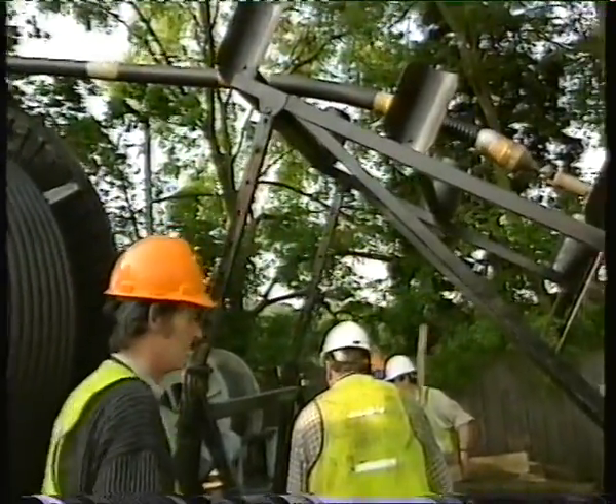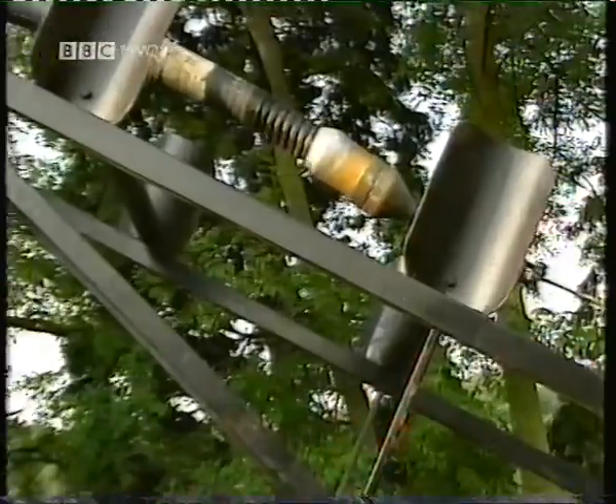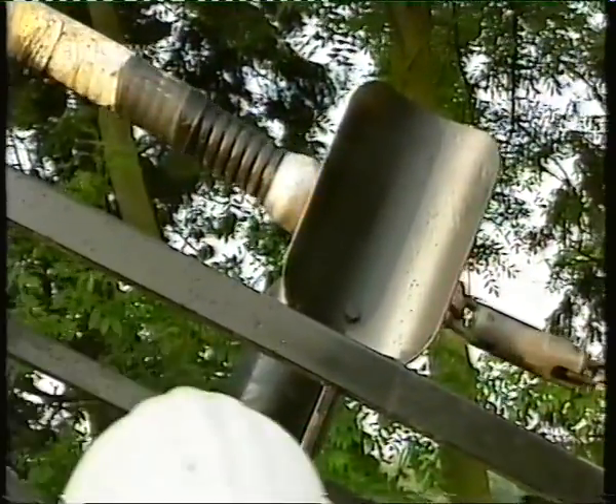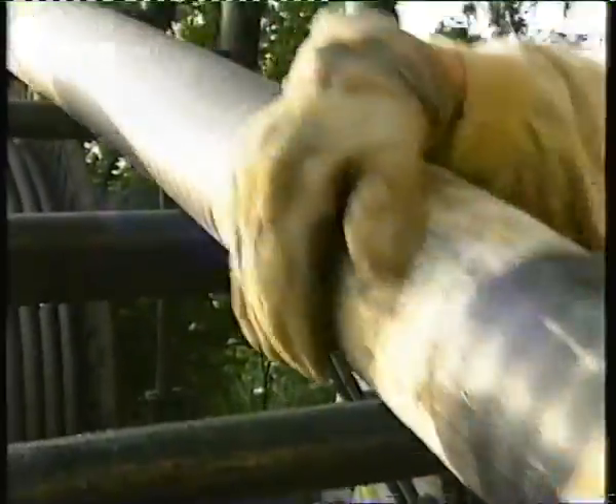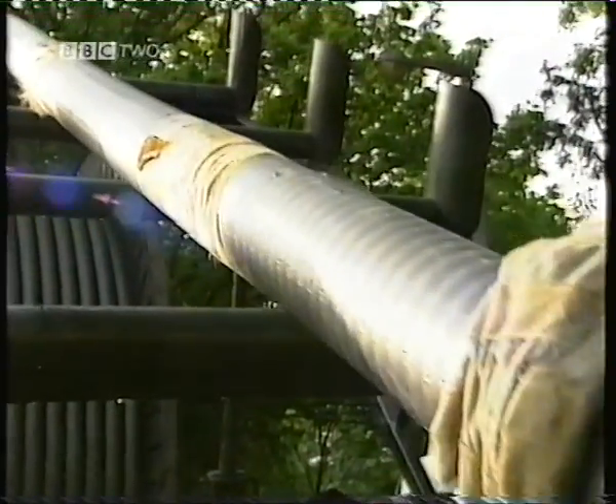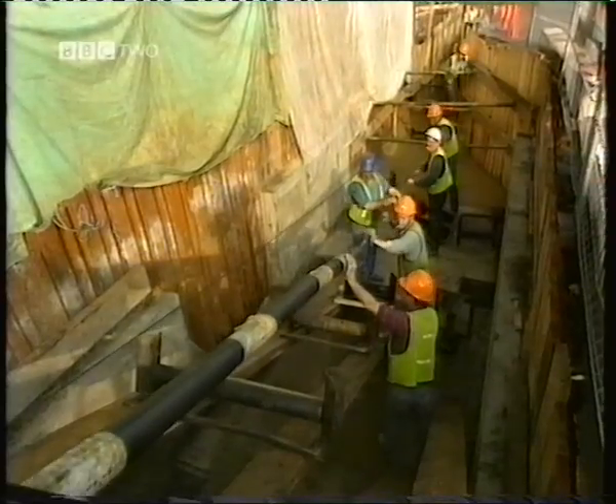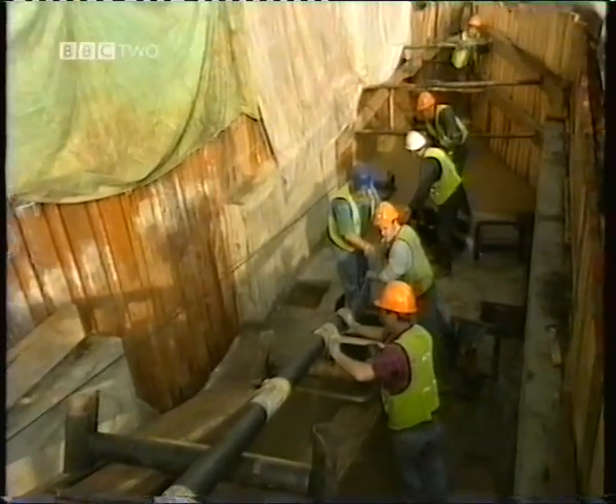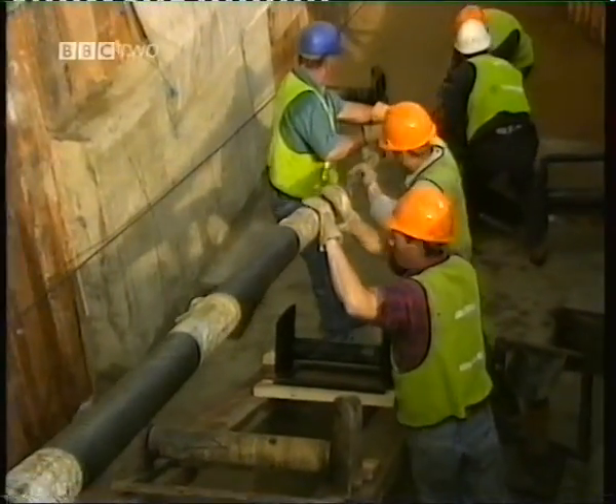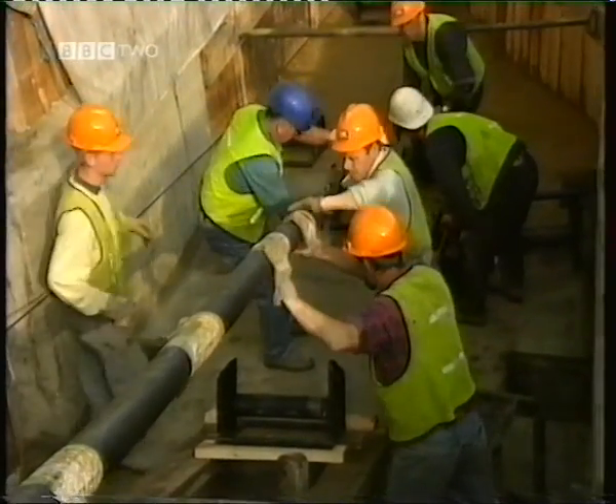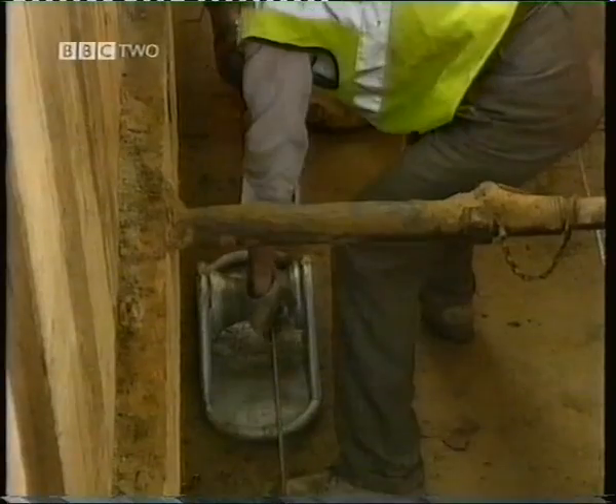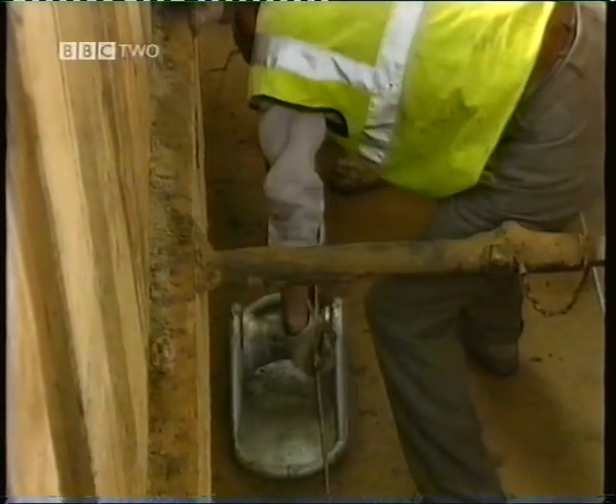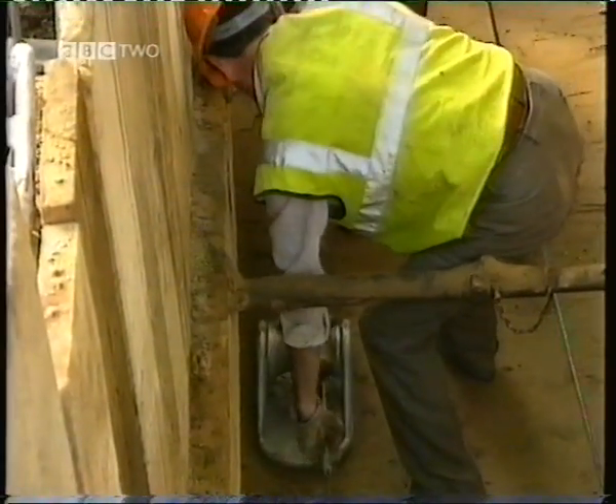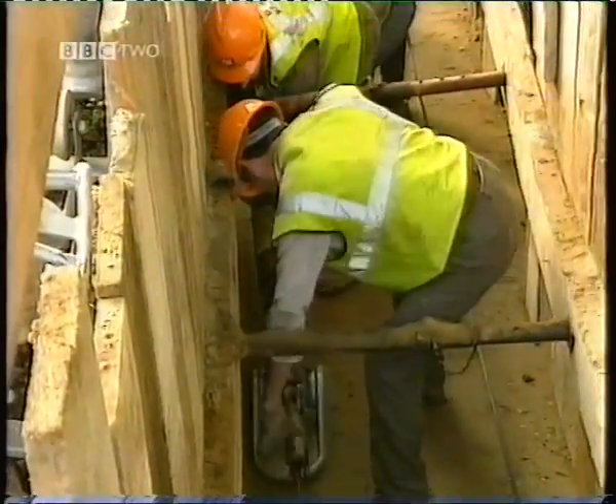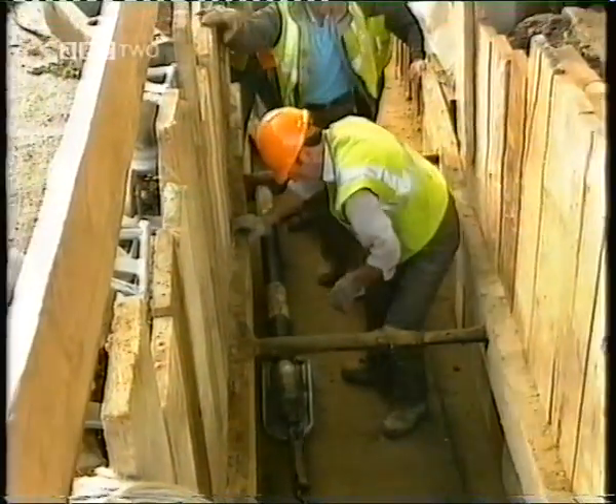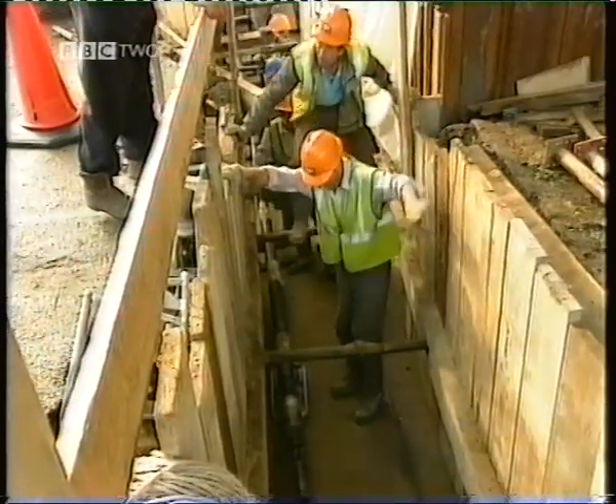In domestic cable insulation, for 200 volts or so, a millimetre of PVC is satisfactory. But for hundreds of kilovolts, that would scale to a PVC cable of over 1 metre thick, hardly practical for installation. And there's the problem of removing some tens of watts of heat per metre. What we want is an insulator with a certain amount of mechanical flexibility and a reasonable thermal conductivity. Covalently bonded liquids, oils, mechanically stiffened with paper, are in fact the insulator inside this cable. We'll see how it's made in a minute.